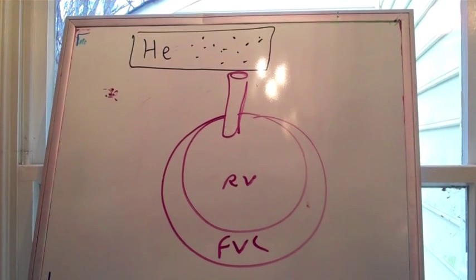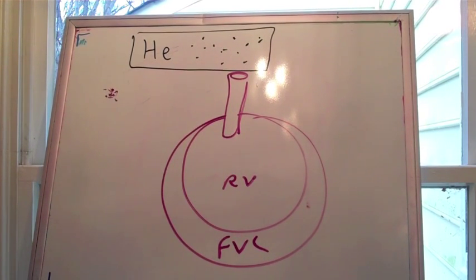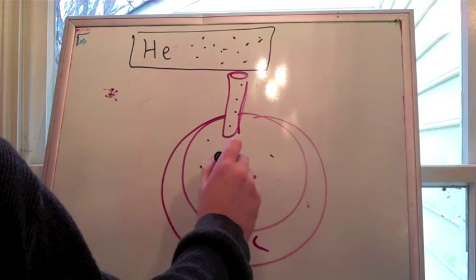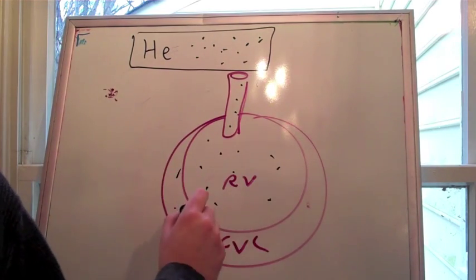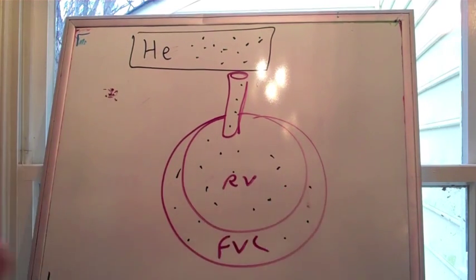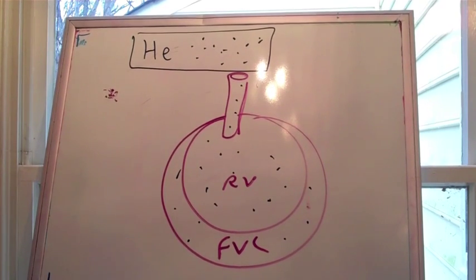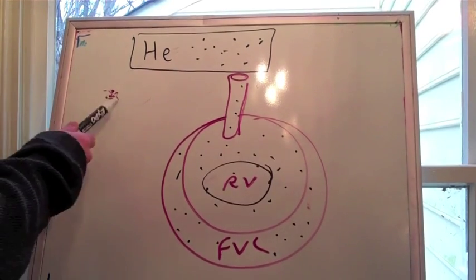The other method is this helium or nitrogen dilution. And essentially, you have a known concentration of helium in a tank. You have the patient breathe in. And that helium kind of disperses and equalizes everywhere. And you know your starting concentration and your ending concentration in your canister. So that allows you to measure the volume.